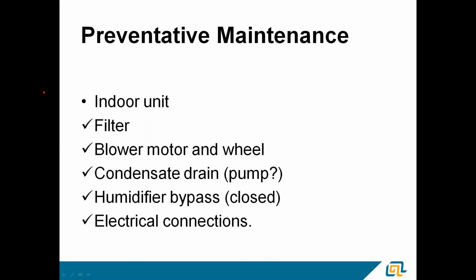If there's a pump, make sure the pump is in operation. And if there's a pump safety, make sure the pump safety is working as well. While I'm down in the basement, I always think about the humidifier bypass. Make sure it is closed if they have a bypass humidifier. And take a look at the electrical connections. This is kind of an unusual one because, of course, you want to make sure the connection has its integrity, that it's good, it's solid, we don't have any broken or loose or damaged wires. But on some systems, you almost want to make sure it's wired correctly. I've run into a lot of systems, 3-4 years old, that were never wired correctly at install, and the consumer's been limping along with it. Just take a look, make sure it's wired the way it should be.